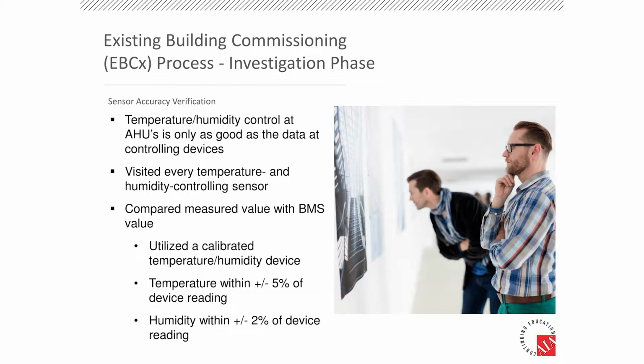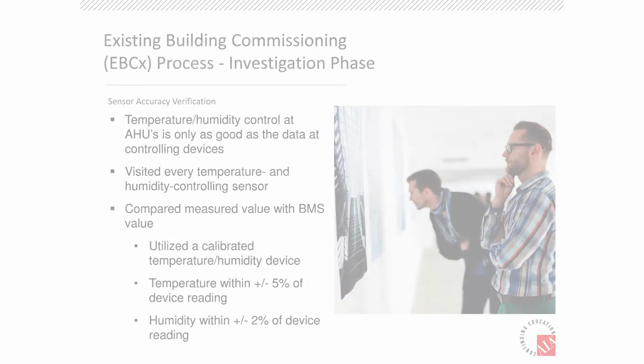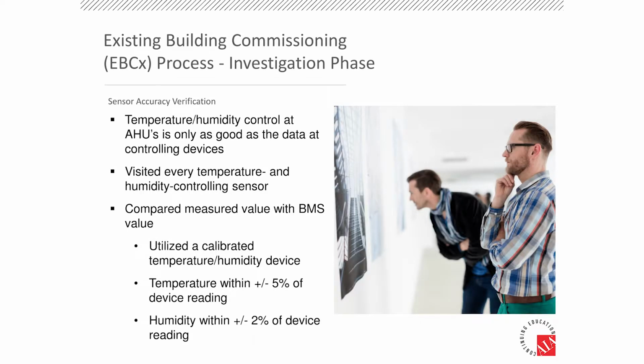Next up was sensor accuracy verification, and this one is really important - I feel like it's an easy one to forget. But as Ryan said, garbage in, garbage out. We're controlling our air handling units, humidification, dehumidification, temperature control, based on the aggregate of information about the climate inside the galleries. So if you've got temperature and humidity sensors that are out of calibration or reading incorrectly, your control operation is going to follow that bad data.